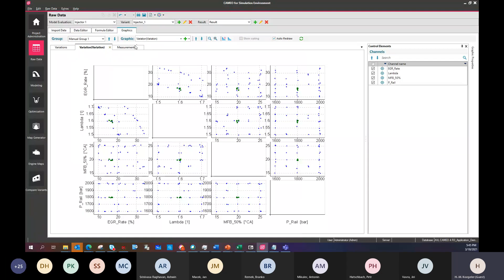And if you then go to measurements, in the raw data, you can just judge whether you have strong outliers or not, or maybe zeros or infinite values. If the smoke meter doesn't respond, PUMA delivers 10 to the power of 9. You clearly see this. You have also additional options for outlier detection. And you have here a repetition point statistic. You see the standard deviation of the repetition point, so how well you can reproduce the several events. Okay, if it looks like that, nicely covered space, no big outliers, at least for the 3 things we might be interested in. We are interested in more, peak pressure also and so on, but I don't go through all.